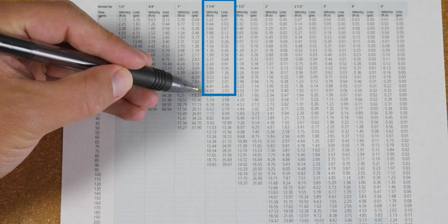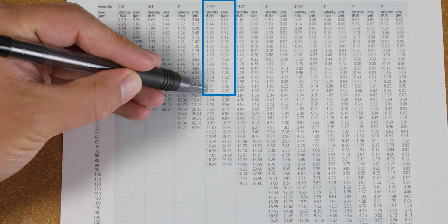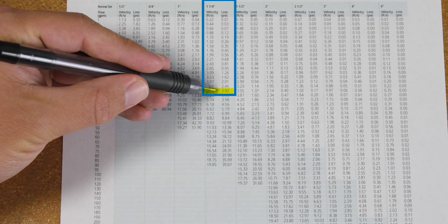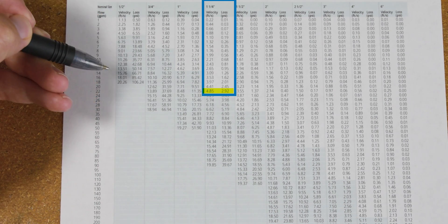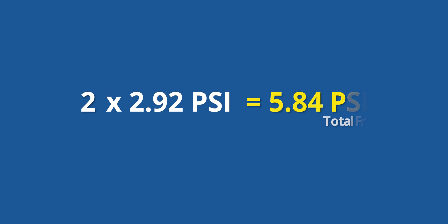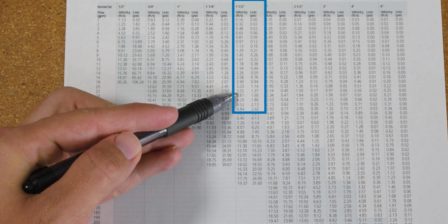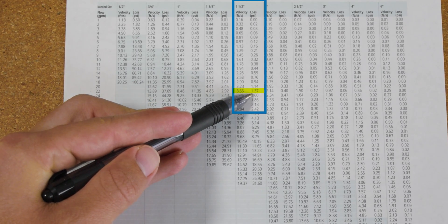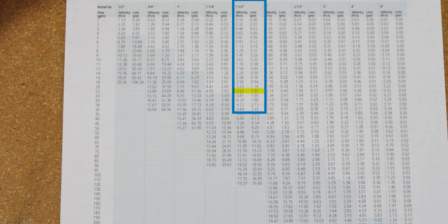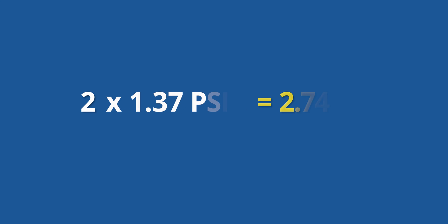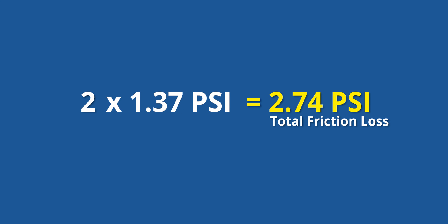For our sample system, the smallest pipe size we could use is one and one quarter inches — where the velocity is at 4.85 feet per second and the friction loss is 2.92 psi for every 100 feet of pipe. Our sample system uses 200 feet of pipe, meaning our total friction loss is 5.84 psi. If I want to minimize these further, I could bump it up to one and a half inch pipe, which would see a velocity of 3.55 feet per second and a friction loss of 1.37 psi per 100 feet, giving us a total of 2.74 psi friction loss for the 200 feet of pipe.